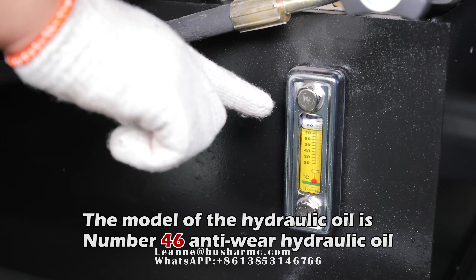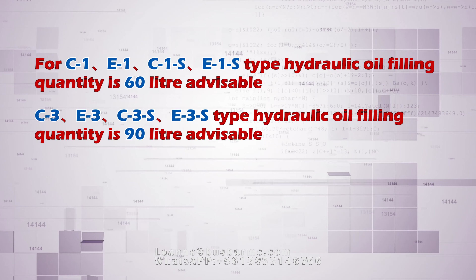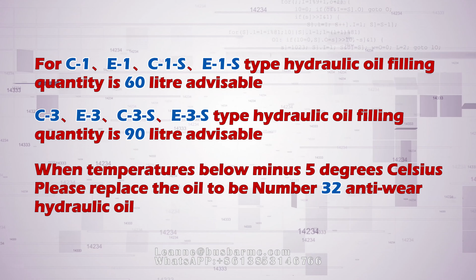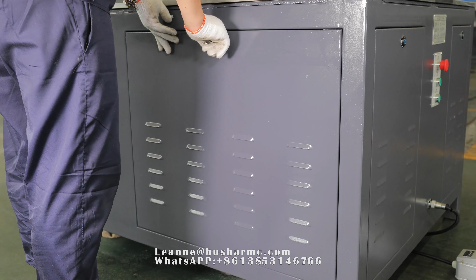For C1, E1, C1S, E1S type, hydraulic oil quantity is 60 litre advisable. C3, E3, C3S, E3S type, hydraulic oil filling quantity is 90 litre advisable. When the temperature is below -5 degrees Celsius, please replace the oil to be number 32 anti-wear hydraulic oil. After filling the hydraulic oil, clockwise tighten the upper cover of the oil port and close the side door plate.